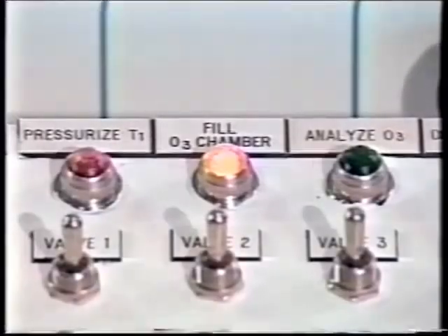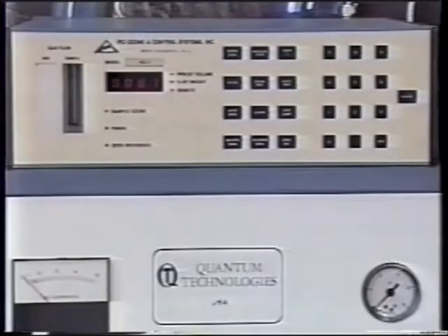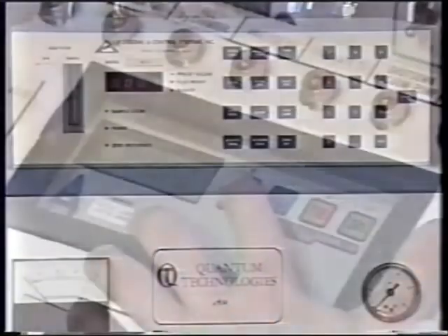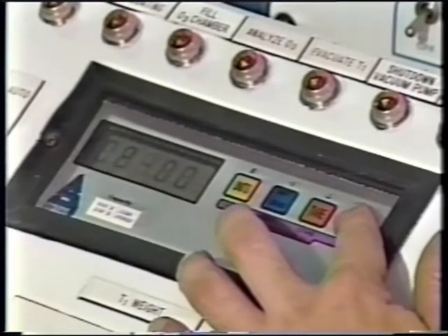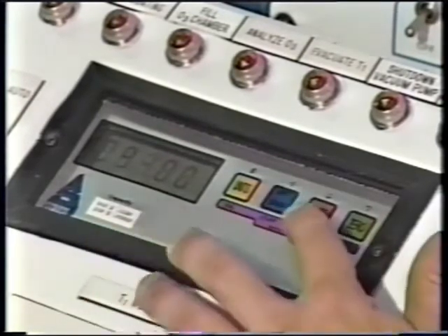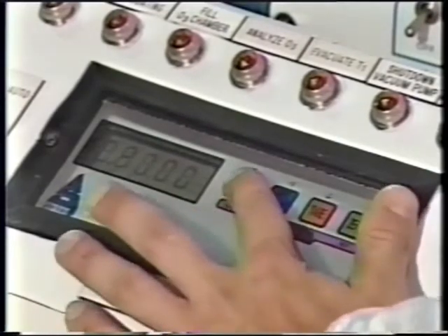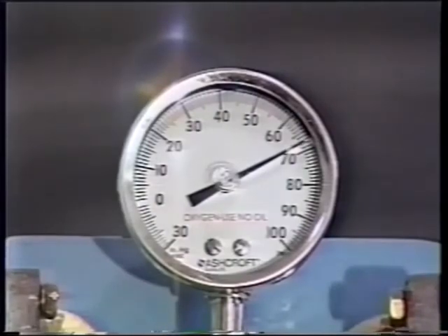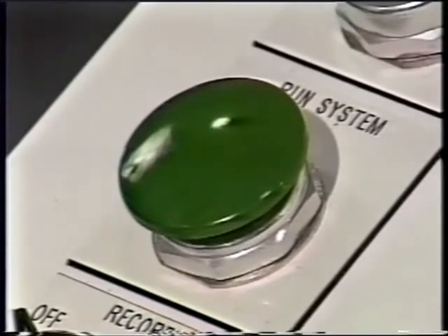Back to the Ozone Caddy — the green light tells us we have ozone ready to use. Now to recheck the strength before injecting. We have calculated the weight of water to be transferred that corresponds to 2 grams of ozone, a 1% charge on 200 grams of pulp, and now input that value to the weight computer. Delivery pressure has been set at 67 PSIG. Hit the green control button, which now makes the predetermined ozone charge available for bleaching.